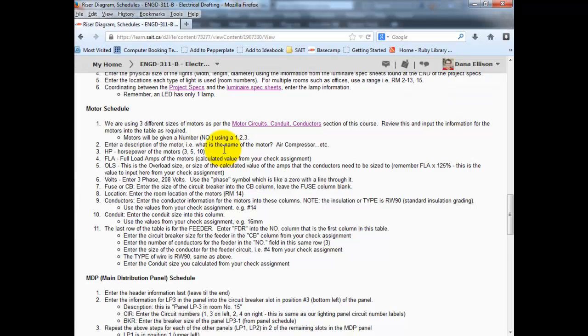The only thing that may not be straightforward that you may not be familiar with is this OLS overload size. So we're going to calculate the value of the amps that the conductors need to be sized to.